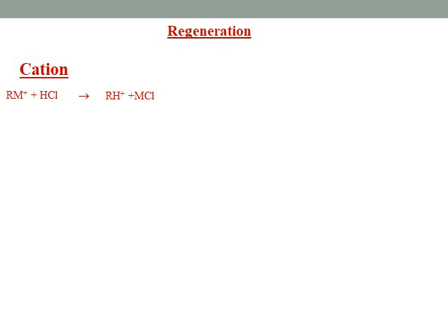Now the HCl contains H plus, an acid, and the H plus will start exchanging M plus. So it will regenerate the bed RH, which is the polymer dispersed with acidic functional groups. RH is regenerated and MCl is released into the water.